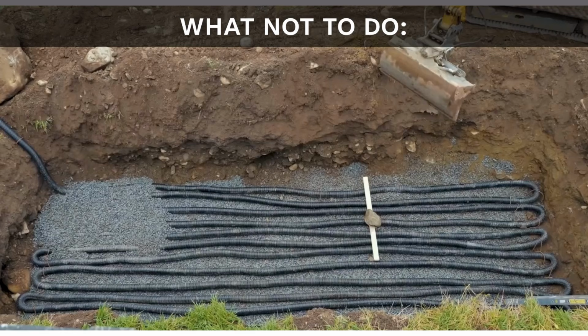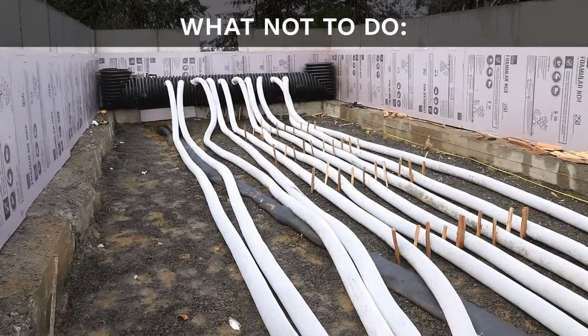And again, this example has a similar issue, but even more extreme. He has very narrow pipe spacing, which is good, but the long length of the tube, only one tube here, one inlet and one outlet, will really reduce the effectiveness of the system. In fact, he may not have even been able to find a fan with enough pressure to push the air through this tube. And the sock. Don't do this. This is not a French drain used to transport water. In a future video, I'll review the many ways to get air into the heat exchanger and to size the fans properly.